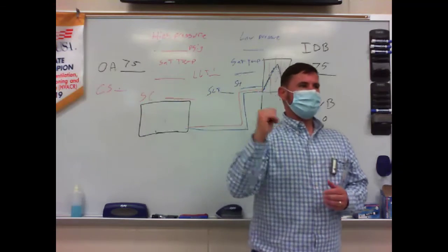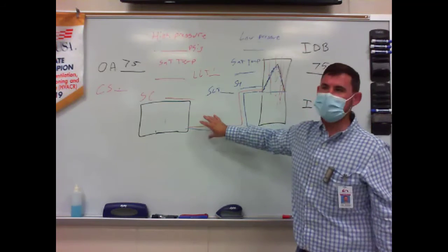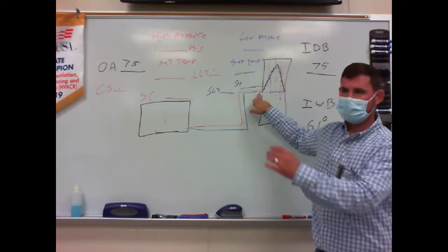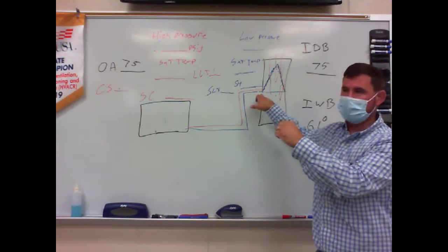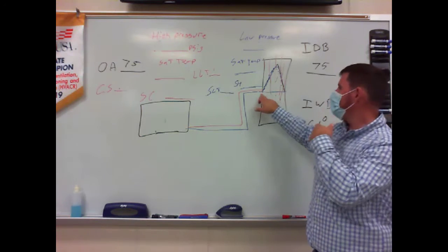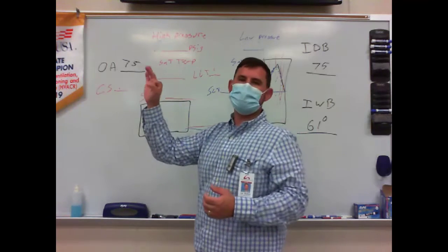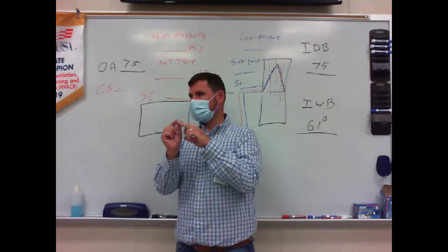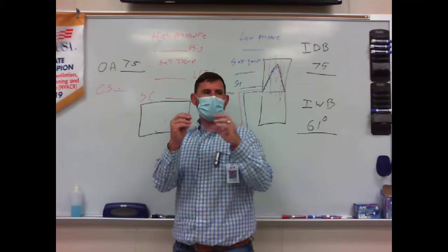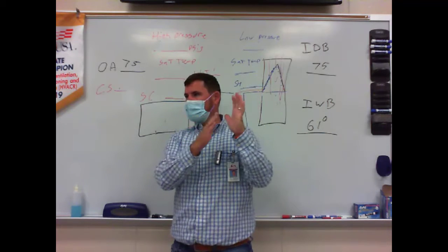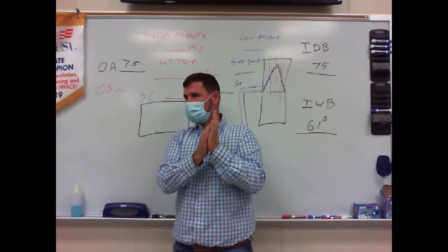All right? So that's going to be different because as I start adding refrigerant with my TXV system, eventually, I told you it's going to block it off, right? It's only going to allow what needs to come through there. Okay? And then it's going to start backing up in the condenser. However, if I have a fixed metering device, that piston has a tiny bore inside of it, a tiny hole, it's going to allow however much high side pressure is pushing on it. The higher the high side pressure, the more refrigerant is going to be forced into my evaporator coil, right?